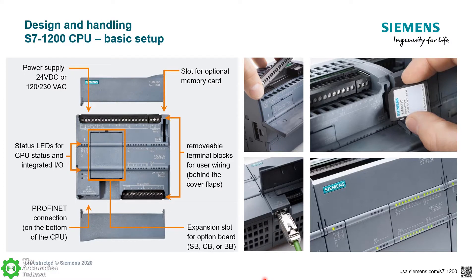The basic design of the 1200 is a typical brick-style PLC. You have integrated digital inputs and outputs as well as analog IO. On top of the CPU you'll see the power supply connection — either 24 volt DC or AC voltage. The terminal blocks on the top and bottom are removable and interchangeable with push-in terminals, which is useful for applications with a lot of vibration where screw terminals may not be ideal.